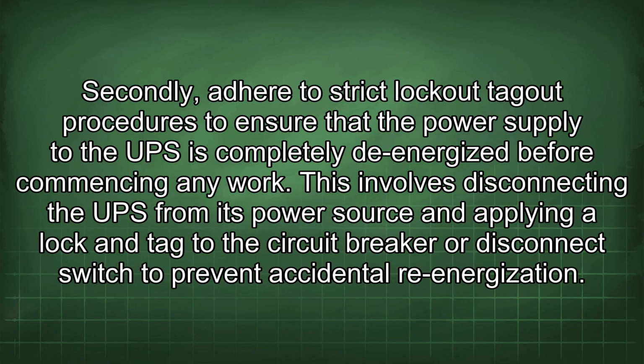Secondly, adhere to strict lockout-tagout procedures to ensure that the power supply to the UPS is completely de-energized before commencing any work. This involves disconnecting the UPS from its power source and applying a lock and tag to the circuit breaker or disconnect switch to prevent accidental re-energization.